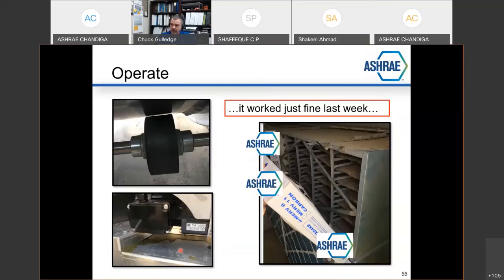And then we went back and looked at the equipment, and we found all these filters completely clogged, completely dirty. The desiccant drum was not able to turn because it wasn't getting traction on the rotating wheel that turns the drum, and the crank that actually turned that shaft was leaking fluid. So this baby was in horrible shape. Lesson learned: make sure stuff is in good shape and does what it's supposed to do if you're repurposing it to do something else. Have I got a deal for you?